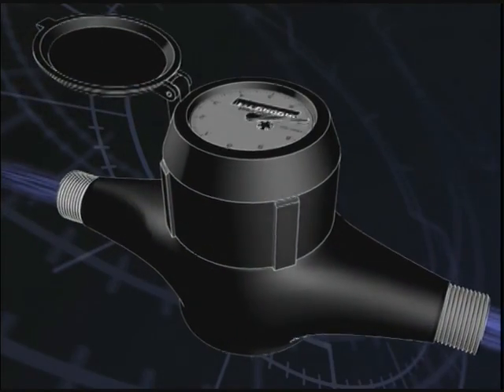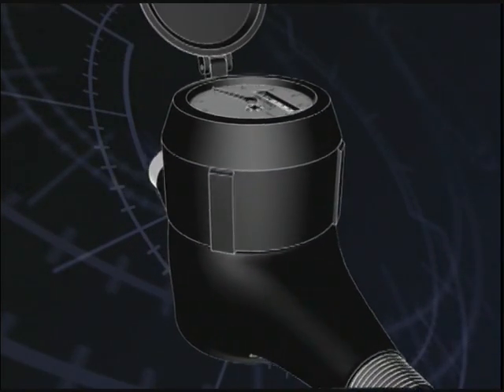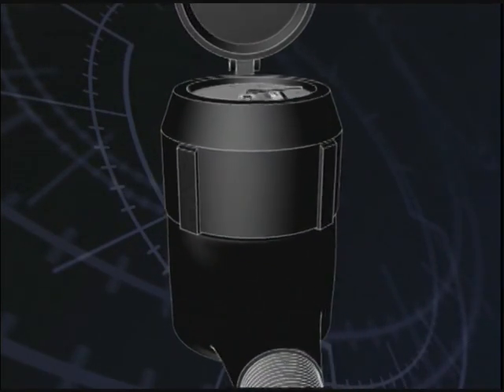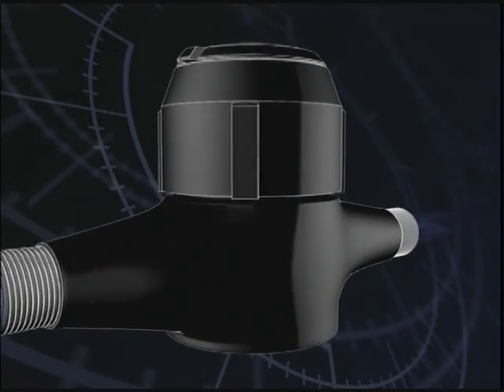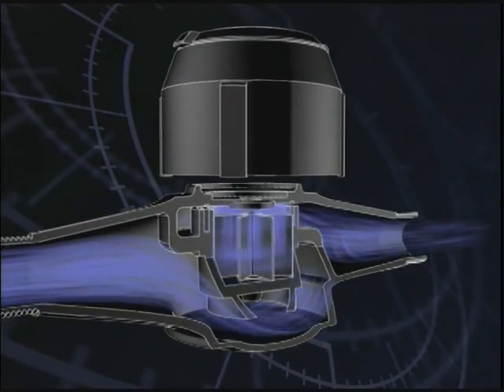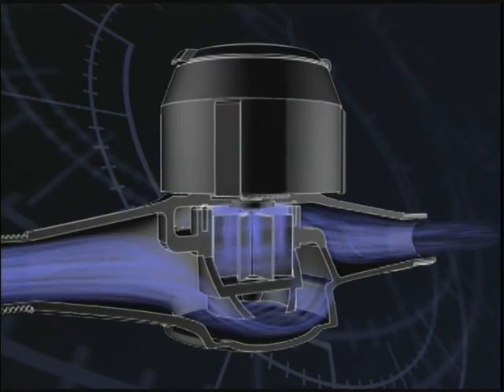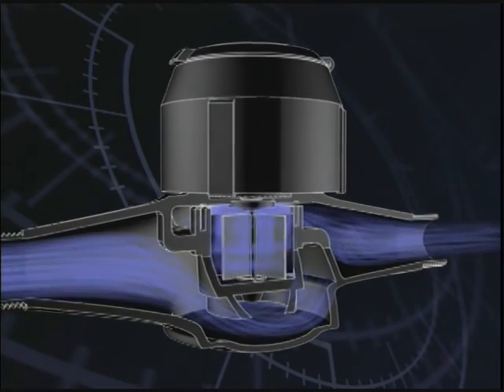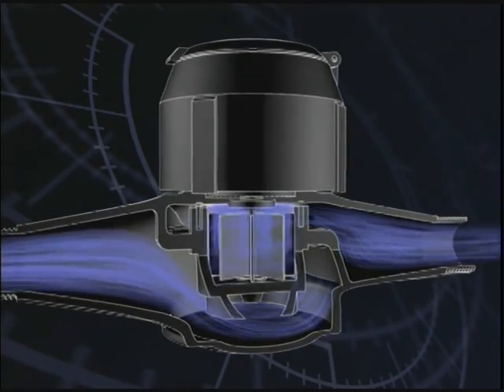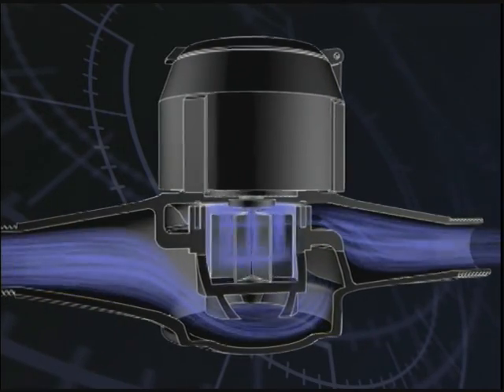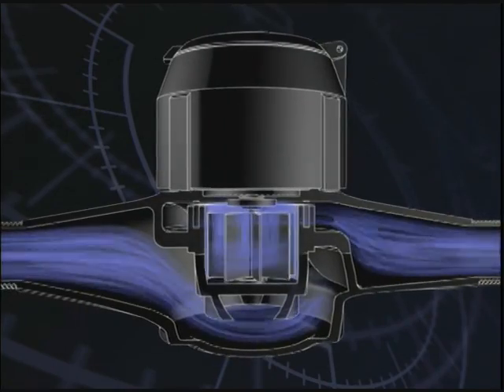Another type of residential meter is the multi-jet meter, which comes in both wet and dry register models. Openings in the chamber direct the water flow across a multi-vaned rotor. The output speed of the rotor is proportional to the quantity of water passing through the measuring chamber.